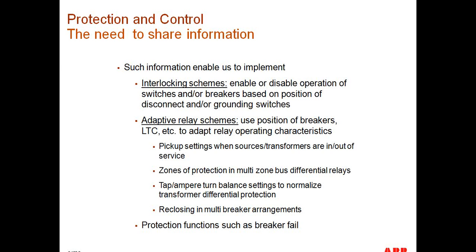Another application where it is important to have an understanding of the topology of the substation is in bus differential relay schemes, where CT current switching may need to be performed internally by the bus differential relay to select the correct currents to add as part of the bus differential relay. Another example could be the position of the load tap changer in a transformer differential protection relay to normalize or to adjust the ampere-turn balance calculation.